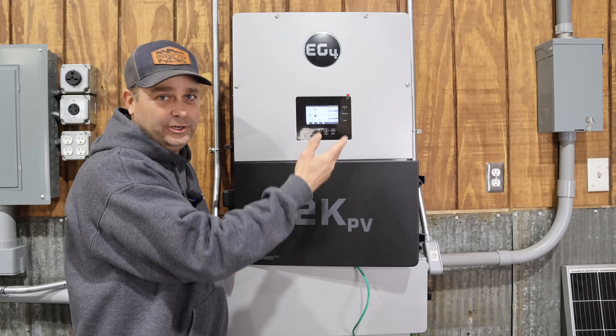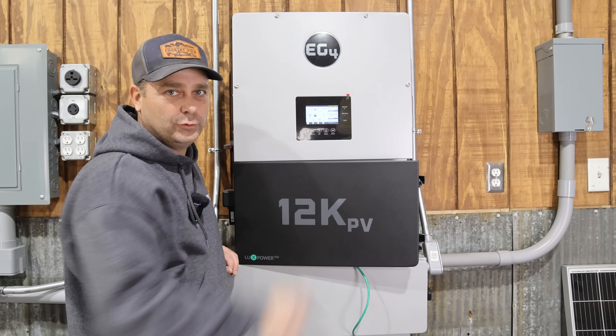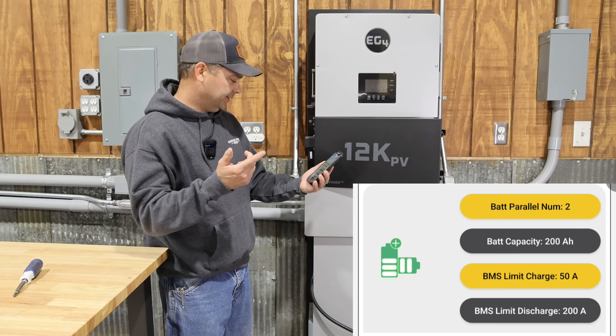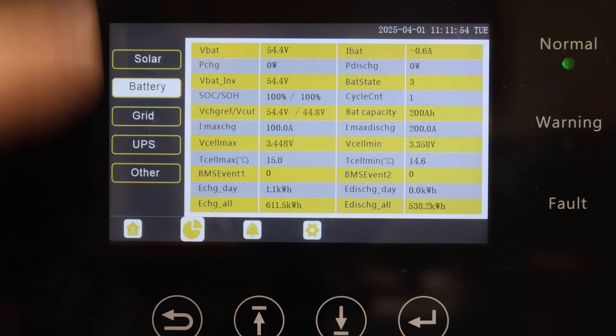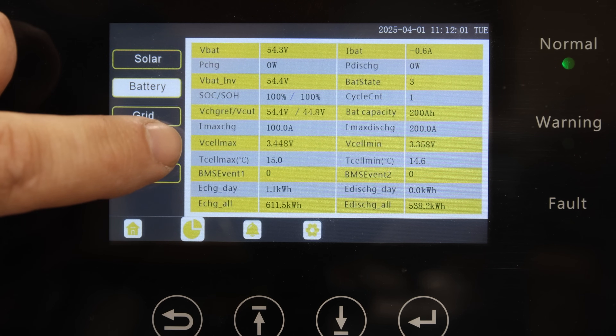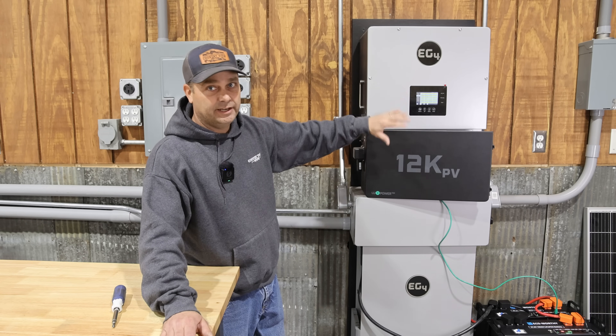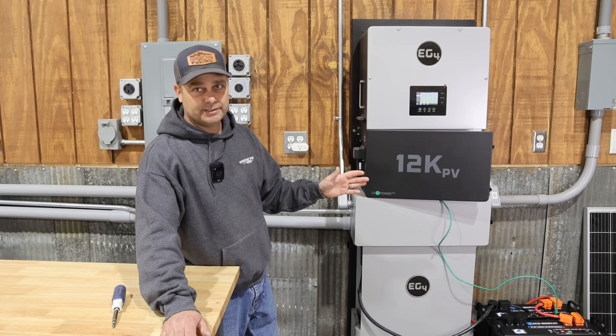The battery symbol went from red to green as soon as communication was established. It says the batteries are at 100% state of charge and 54.4 volts. Pulling up the monitoring app, I can see it recognizes two batteries in parallel with a total of 200 amp hours. Going into the battery screen, with that communication it shows state of charge, total battery voltage, maximum and minimum cell voltage, and min/max temperatures — all the battery information is populated and appears correct, so the communication between the inverter and the batteries is working properly.